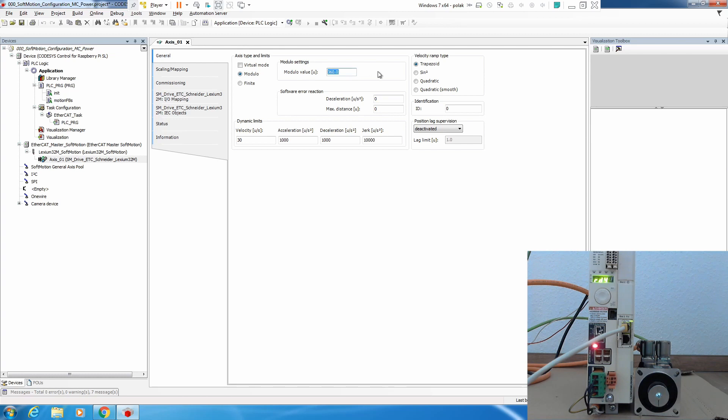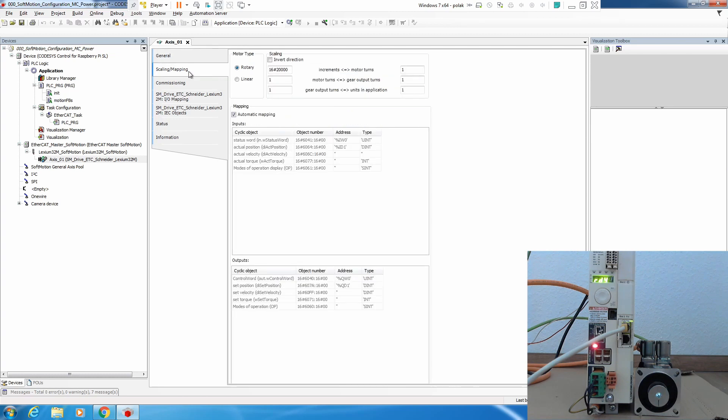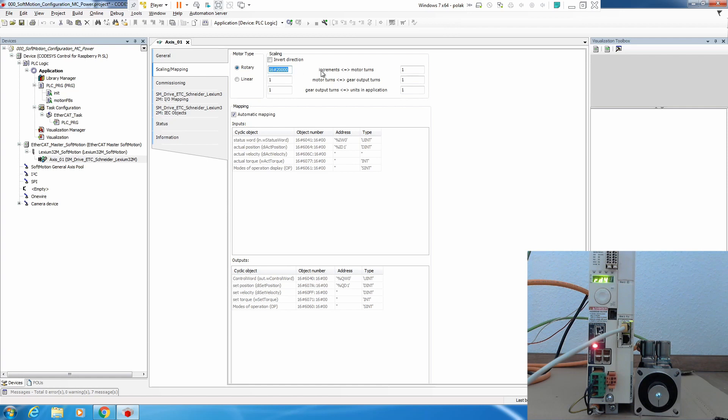Now to make a scaling correct we click on scaling and here we have motor type which is rotary. We see that our motor is rotary motor and now we have number of increments. This number here is actually the real number of position scaling inside our drive and we want to make it 360 units in our application which will represent degrees. Now we can start to program our move velocity.